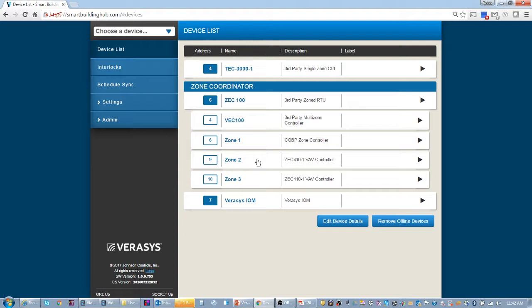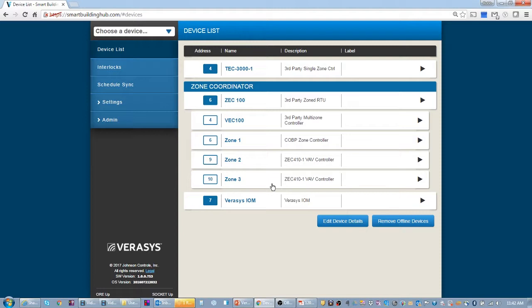Then once you plug it on and bring it up, if for some reason, let's say this all went down and it went offline, you'd find your trunk problems one device at a time. Whereas if you brought it all up, just kind of like what I did, I at least know I have no wiring issues. I know I have no address conflicts. You can weed through your problems one controller at a time and it becomes more efficient and you do a better job of bringing it up.